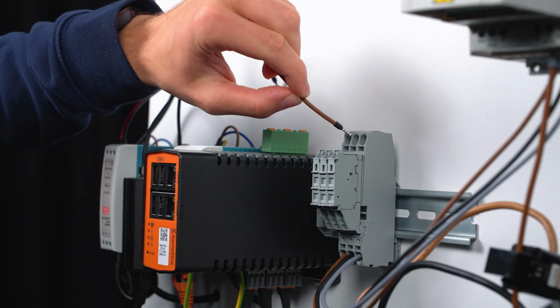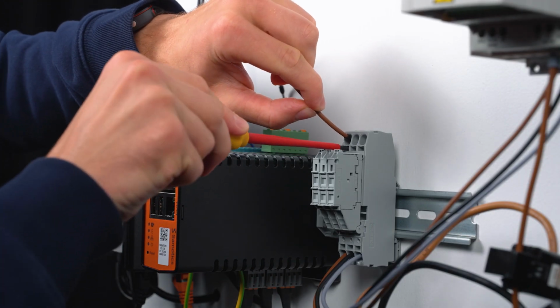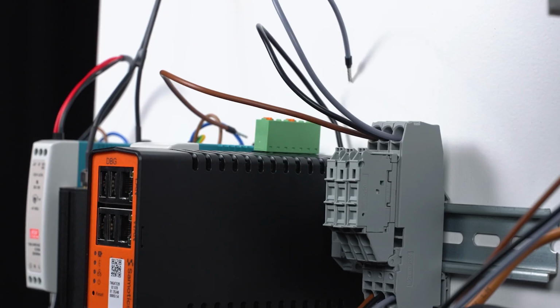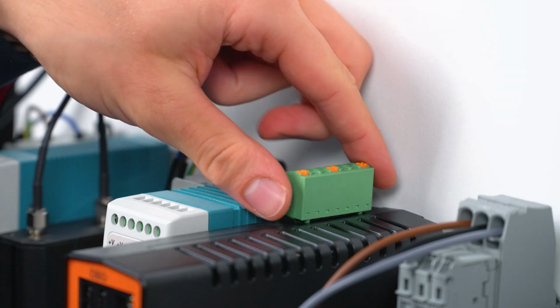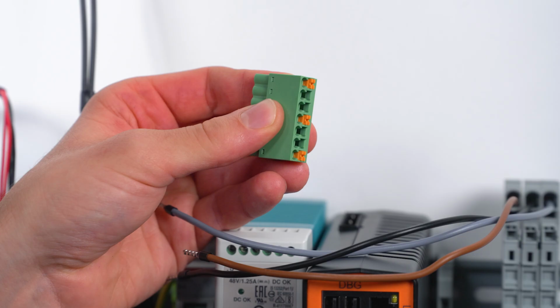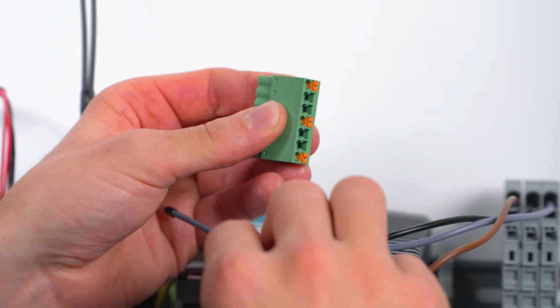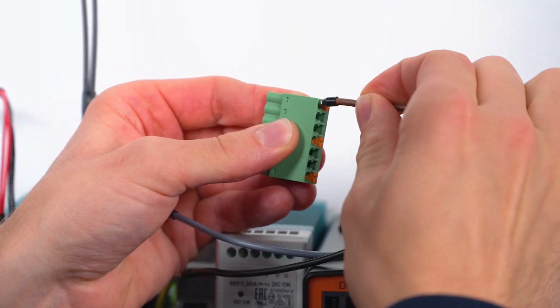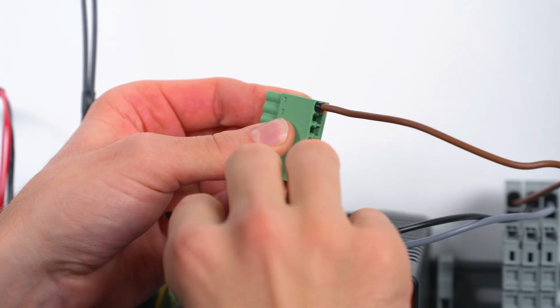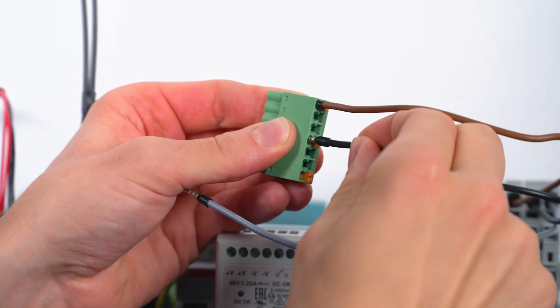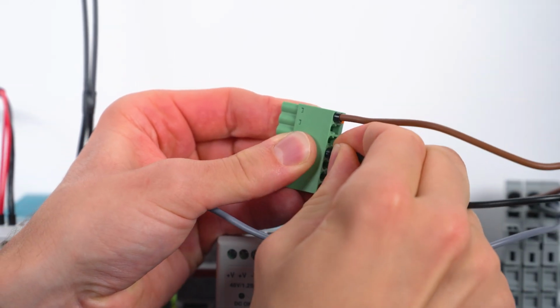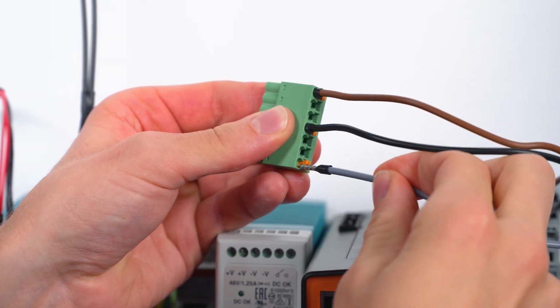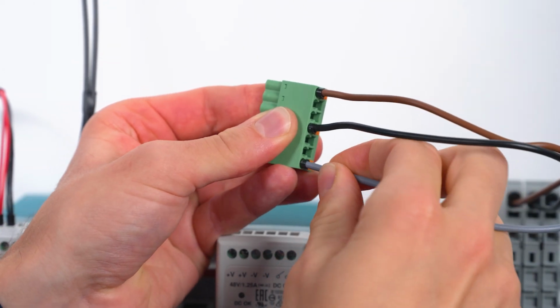Then connect a second set of wires to the opposite side of each fused terminal block. Insert the free ends into the voltage connector at ports 1, 4, and 7 of the 7-pole push-in connector, following the same order as for the current transformers. Phase 1, brown, closest to the DIN rail, Phase 2, black in the middle, and Phase 3, gray, furthest from the DIN rail.